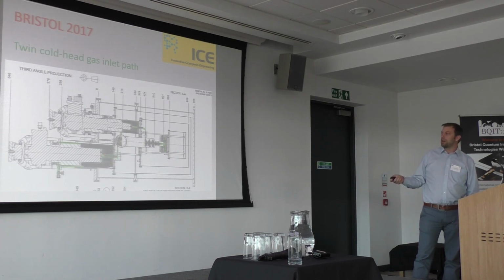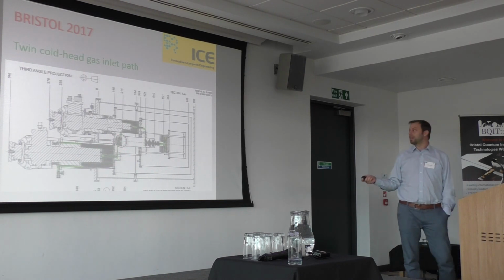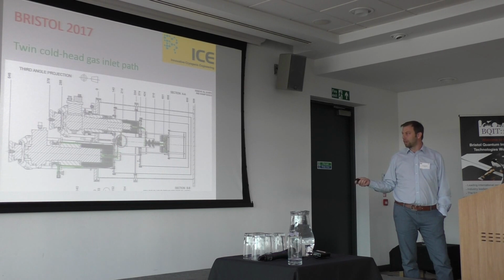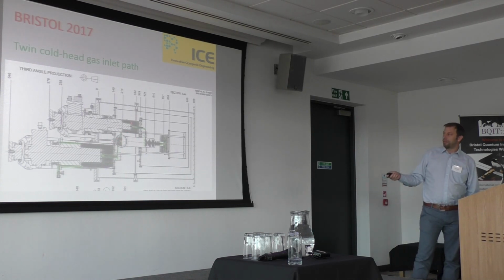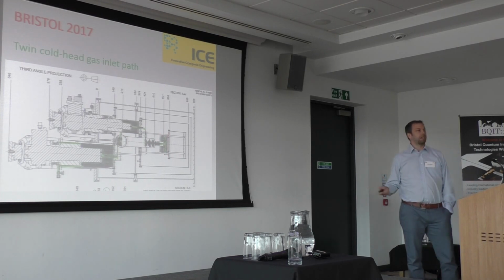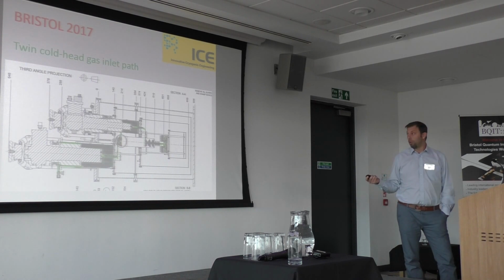It then goes into a cassette which is embedded within the 1K pot pumping line itself, because of the cold gas coming out of the 1K pot, you're getting a lot of free cooling from that. Feeding it into the next cold head, which is at 4.2K, but we're trying to get it as close to 4K as we can before it goes in there. Once we've liquefied it at the 4K stage, we're feeding it back into the pumping line for a second time at a colder part of the pumping line, so it's as close to 1K as we can get it before it goes into the 1K pot. So this is minimizing the pretty big heat load from the warm helium-4 coming back into the 1K pot, so we're really pushing that very hard.